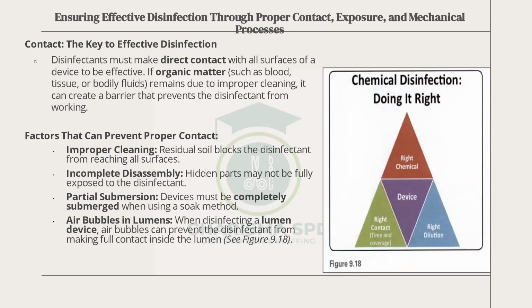Now, partial submersion. I just talked about that. Especially this happens if you are using the manual kind of HLD. If the machine is down and you are using a basin just to put the scope in, you must make sure that the chemical is above every part of the scope. It must be fully, completely submerged. Air bubbles in lumens. Those instruments that have lumens, when air bubbles are coming, it means that there's air. You must make sure that air bubbles are out completely. Then it means that the chemical can go to all other areas. So contact is very, very key. And then exposure as well. Contact and exposure. Every part of the instrument must be exposed to the sterilant, to the high-level disinfectant. Thank you. Next slide, please.